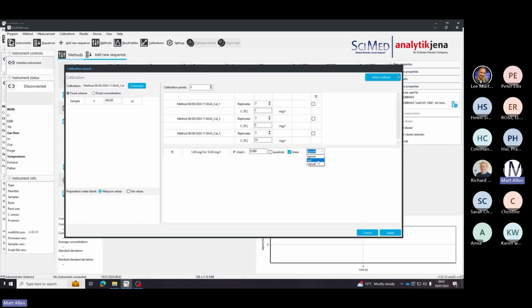So unlike the previous multi-win, where you had to do a calibration, then check the calibration results and then put your sequence on, this multi-win Pro allows you to do the calibration, then go straight into a sample sequence. So therefore we can run the calibration and we can run this linearity check, and the software will have a look at the three states here: ignore, ask, or cancel.